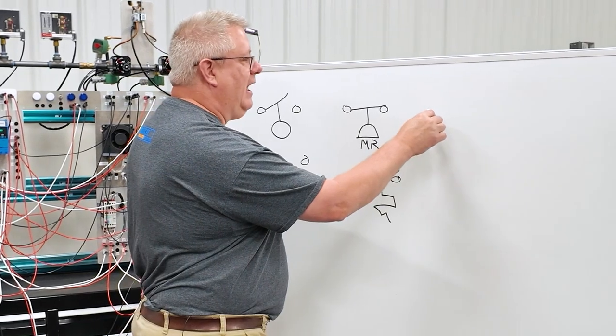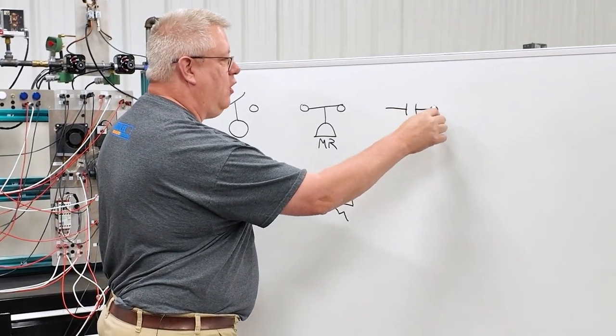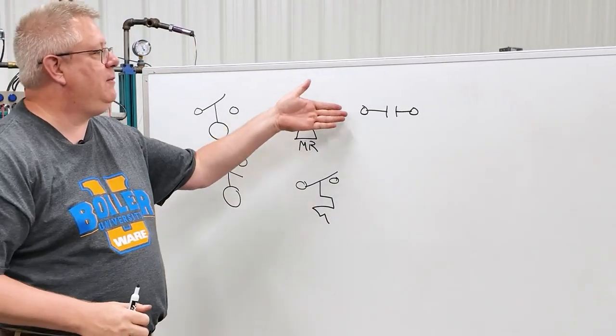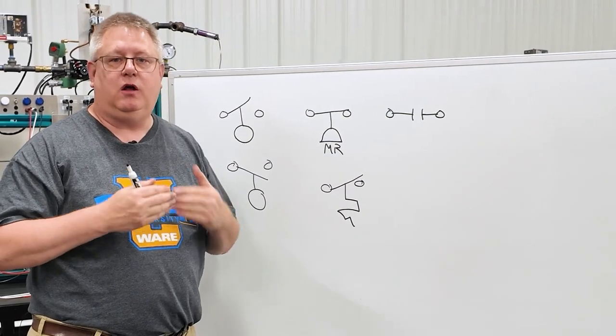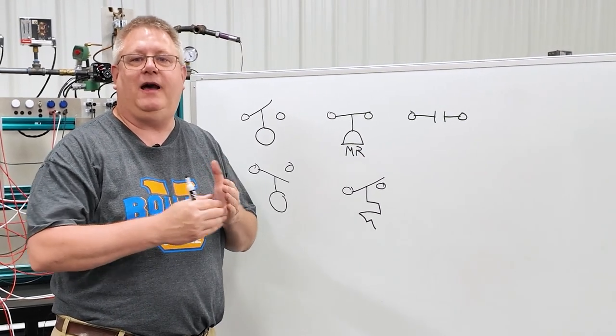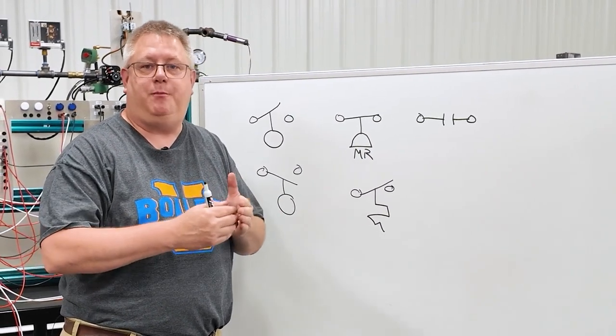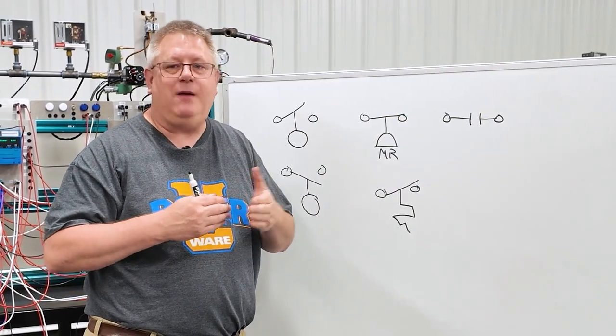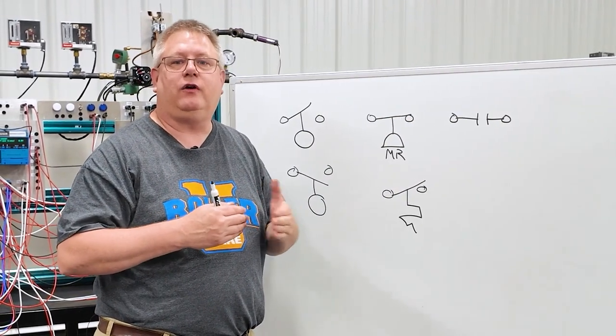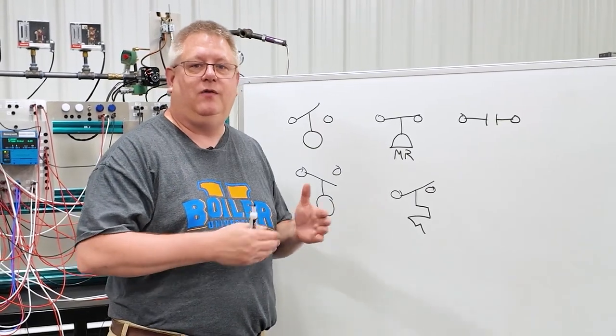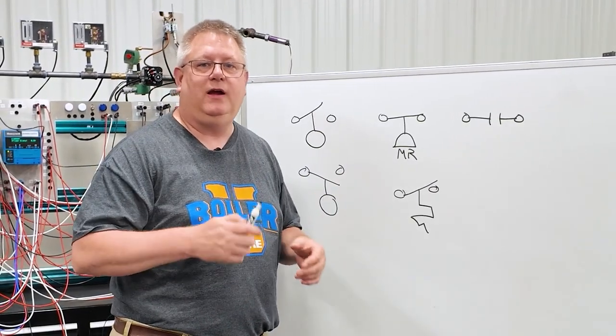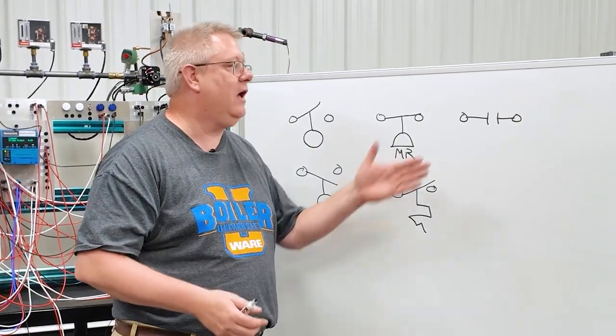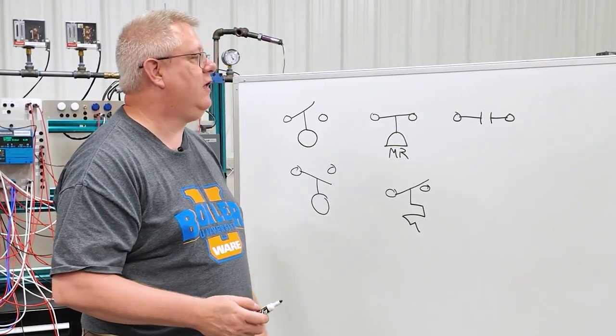If I've got relay contacts, it's going to show up as an open contact. So that would be pretty typical on a probe-style low water cutoff, where we might have an electronic-based switching system. Or it could also represent any type of relay contact in the circuit, whether it's a building management system that opens and closes, or it's a contact on a latching relay alarm or something like that.